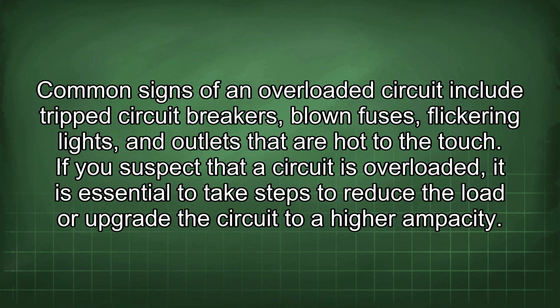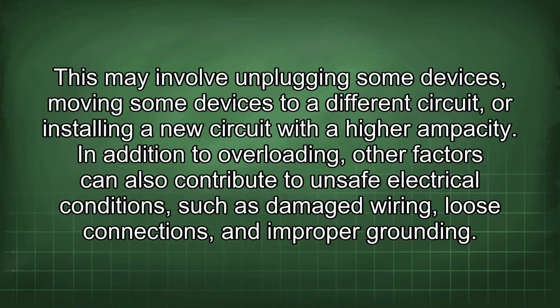Common signs of an overloaded circuit include tripped circuit breakers, blown fuses, flickering lights, and outlets that are hot to the touch. If you suspect that a circuit is overloaded, it is essential to take steps to reduce the load or upgrade the circuit to a higher ampacity.